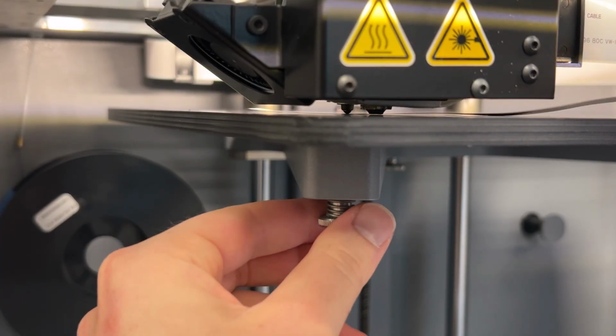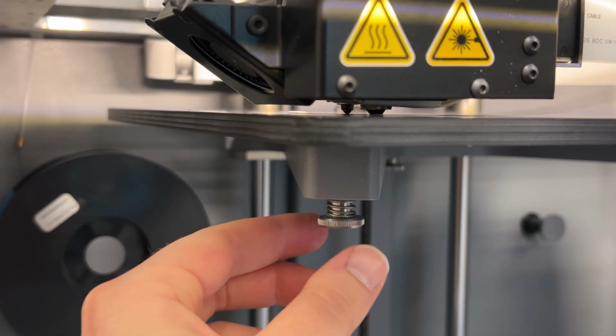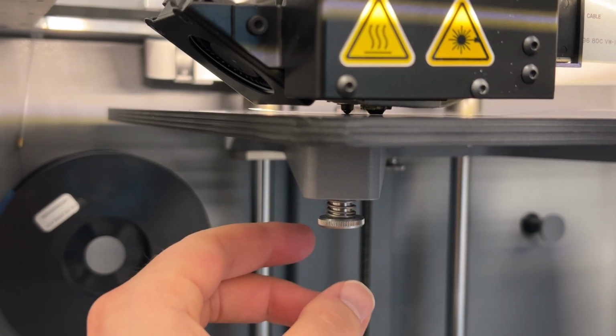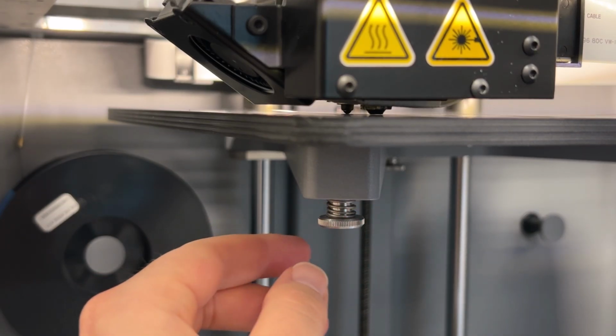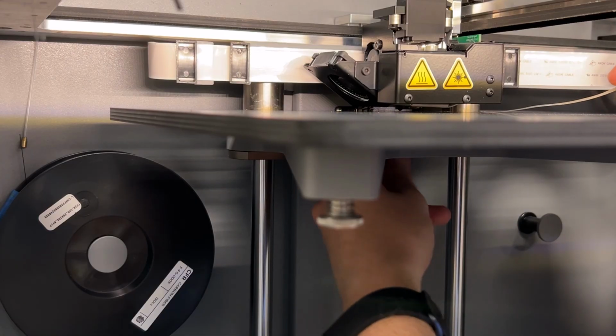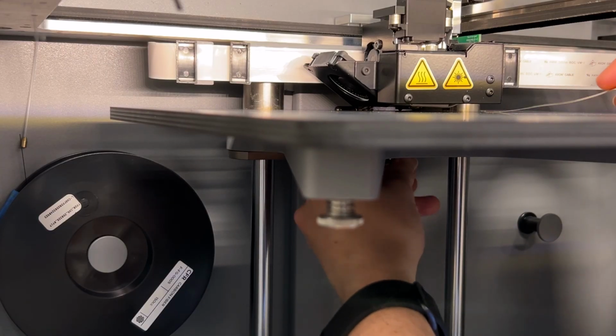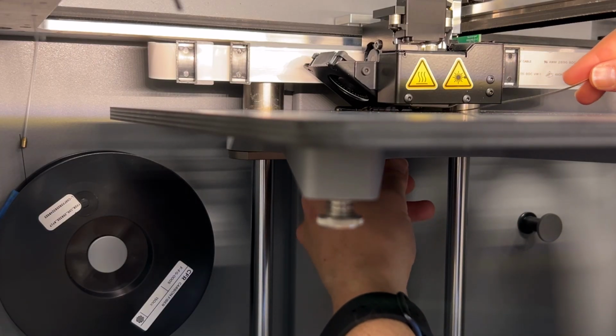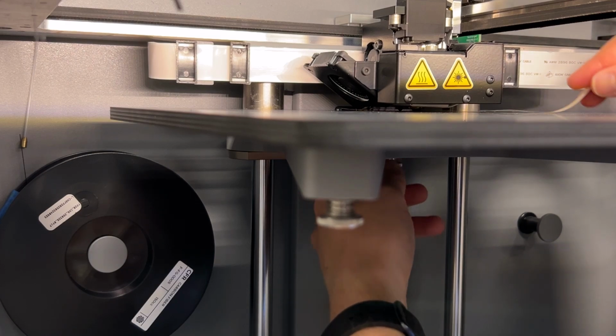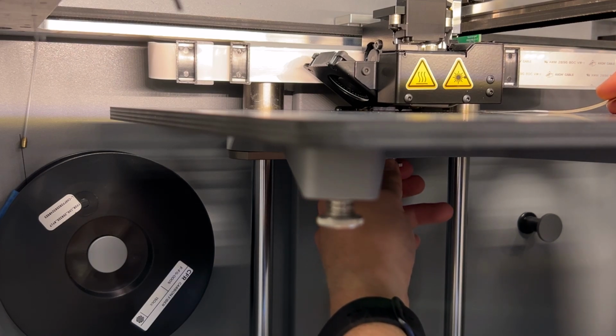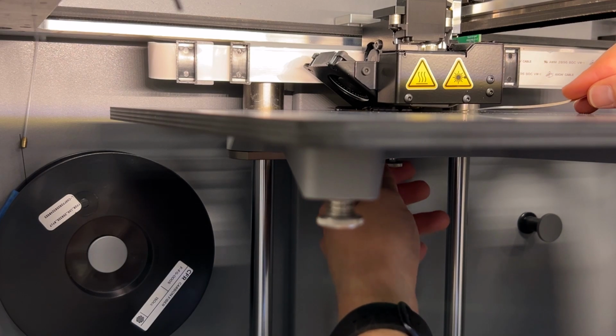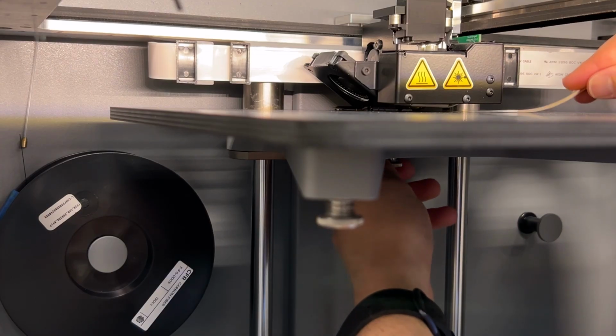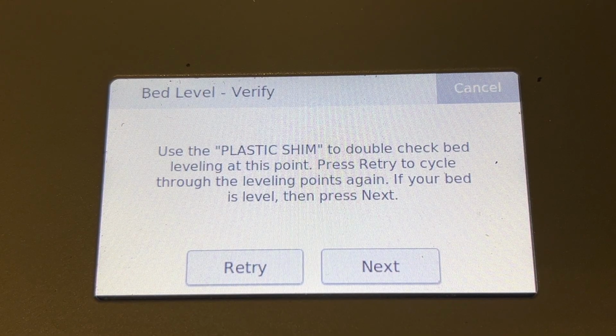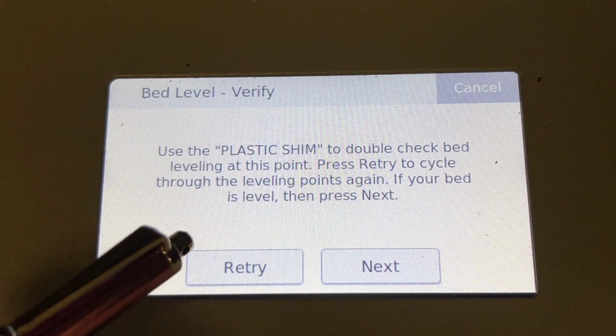As before, we'll repeat this process across the other 2 locations, which are positioned above the 3 thumb screws. And that warning really applies to this center rear location since it's pretty awkward to get to without leaning on something, so try not to here. And do your best with the leveling, but don't fret too much because we'll get a more accurate leveling result later. Now, when asked if you want to retry the shim leveling, I always recommend you do.